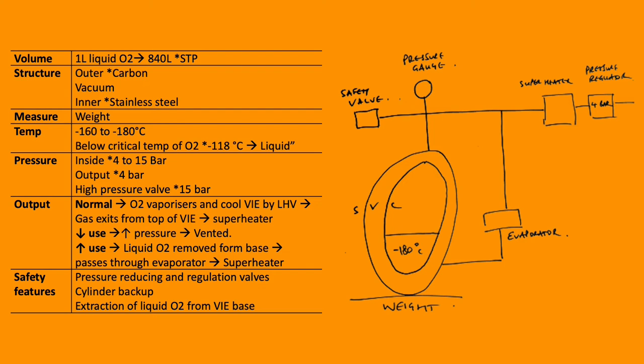Under low demand, the rate of oxygen use is less than the O2 gaseous production. Therefore excess O2 gas is vented by the safety valve.